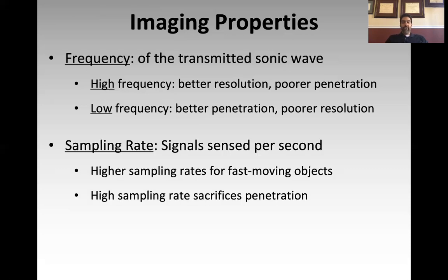The second imaging property is sampling rate. The crystal goes back and forth between being a transmitter of sound and a receiver of sound. The rate at which the machine switches the crystal between transmitting and listening is the sampling rate — the faster it switches, the higher the sampling rate. In general, the purpose of a high sampling rate is the ability to look at fast-moving objects with a high degree of fidelity. For example, if you're trying to look at a valve on a tachycardic heart, a higher sampling rate gives you the ability to do that with high fidelity. You do sacrifice some penetration with a high sampling rate.